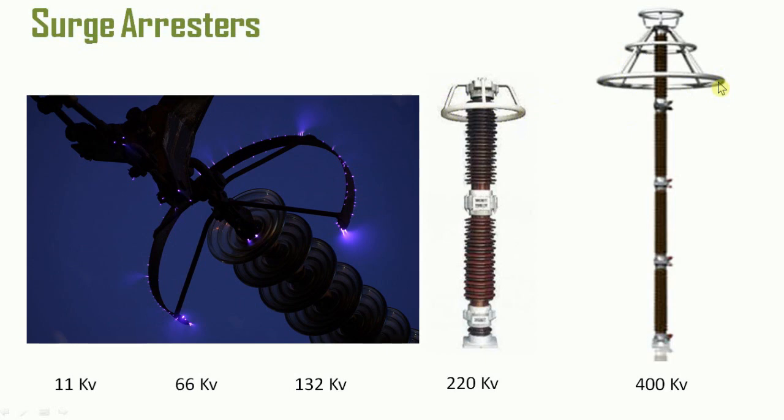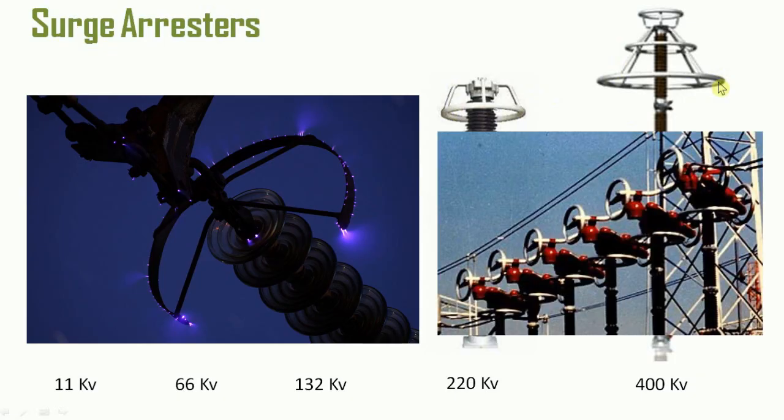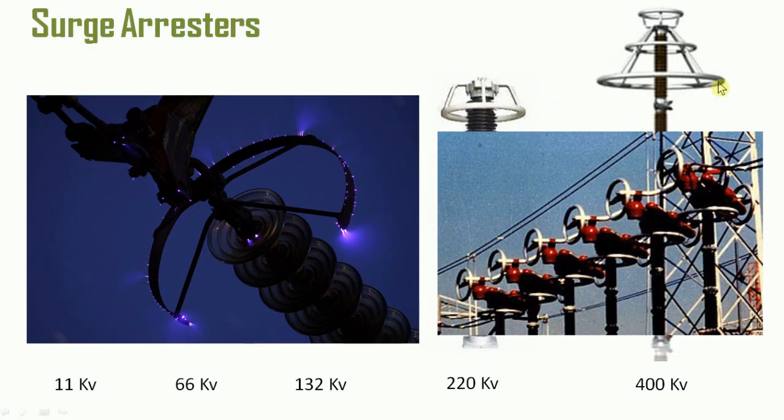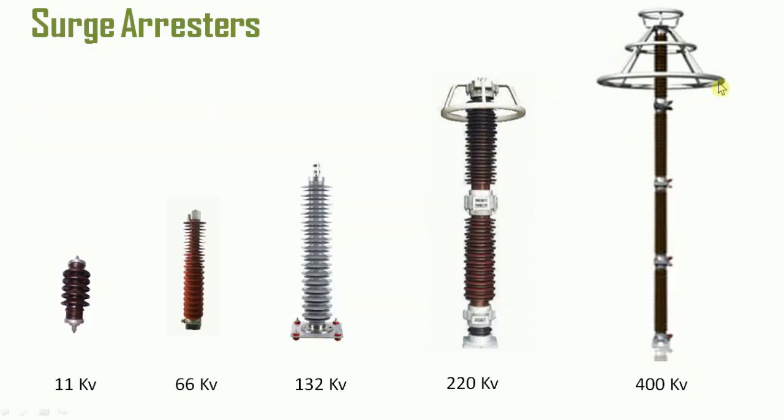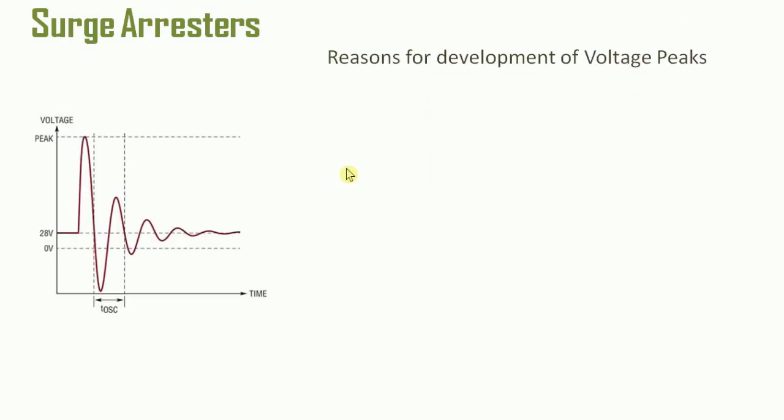To avoid this, not only at the terminals of surge arresters, even at the terminals of equipment in the substation, these rings are provided, known as corona protection rings, which increase the surface area. Therefore, the charge gets spread throughout its surface rather than concentrating at a point. So these rings are installed to reduce corona loss, and it has nothing to do with the working of surge arresters.